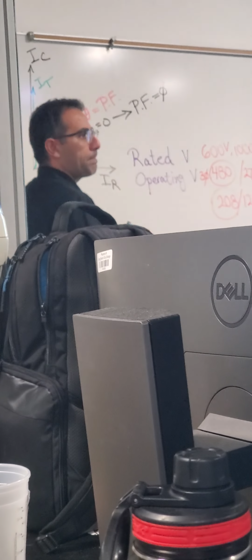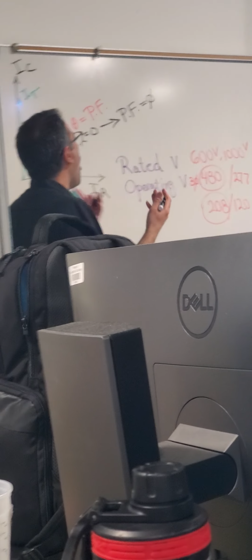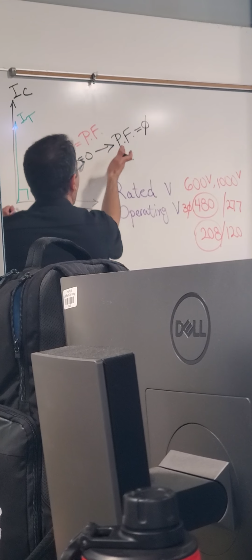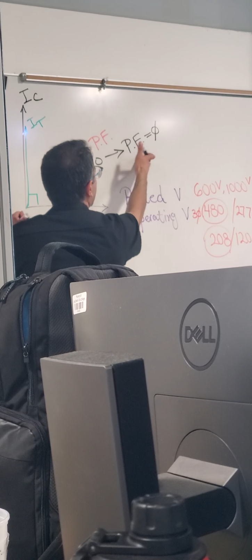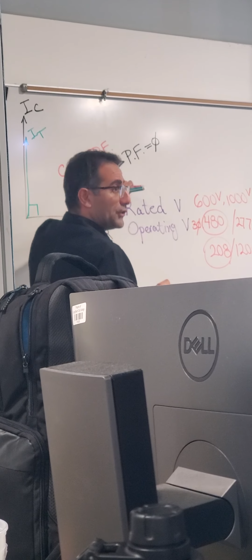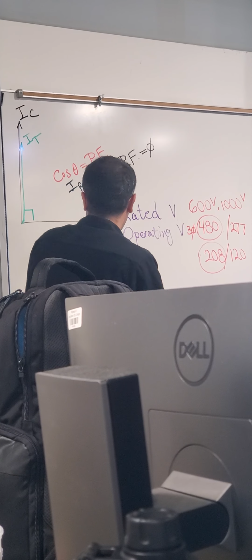In reality, we always have some leakage current. That's why your power factor is not zero realistically. For the insulation, your power factor is always a small amount.